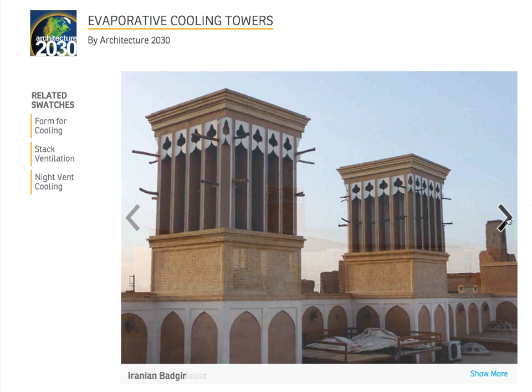The nice thing about the passive downdraft form is, number one, it doesn't use a fan to drive the air through the building, and number two, it gives the architect a nice opportunity to work with a vertical form. The evaporative cooling is also going to work when it's too hot outside to ventilate. So it could be 100 degrees outside, 105 degrees, and by cooling off the air through evaporative cooling, you can bring it back down into the comfort zone. You can also use it in a kind of indoor or indoor-outdoor situation, either one.